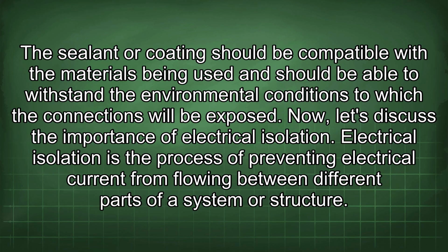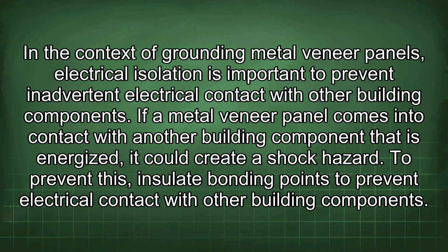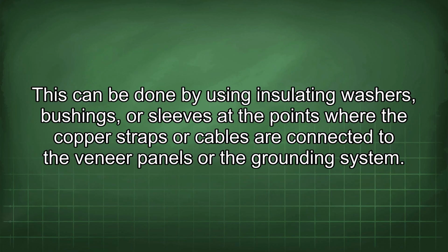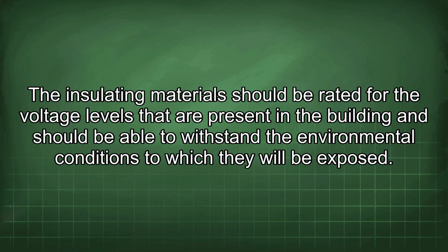Now let's discuss the importance of electrical isolation. Electrical isolation is the process of preventing electrical current from flowing between different parts of a system or structure. In the context of grounding metal veneer panels, electrical isolation is important to prevent inadvertent electrical contact with other building components. If a metal veneer panel comes into contact with another building component that is energized, it could create a shock hazard. To prevent this, insulate bonding points to prevent electrical contact with other building components. This can be done by using insulating washers, bushings, or sleeves at the points where the copper straps or cables are connected to the veneer panels or the grounding system. The insulating material should be rated for the voltage levels that are present in the building and should be able to withstand the environmental conditions to which they will be exposed.